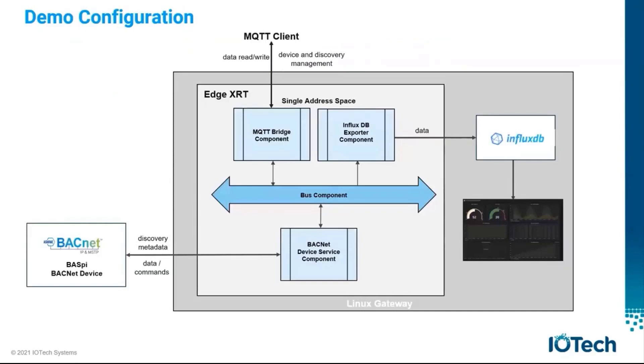This slide provides a pictorial representation of the demo configuration. The XRT deployment, which is running as a native executable, consists of three standard components: a BACnet device service component to provide connectivity to the BASPi BACnet device, an MQTT bridge component which is used to support the standard management API, and an InfluxDB exporter component which is used to write the BACnet device data to a local InfluxDB database instance. All of the demo is running on a Linux Edge gateway connected to the BACnet device over TCP/IP.